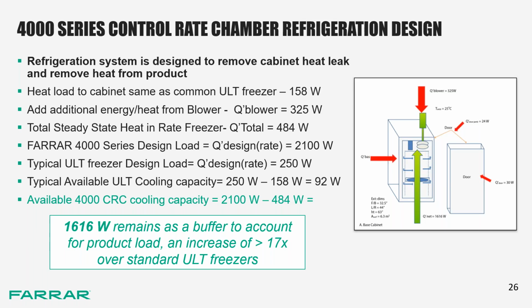As a forced air convection freezer, the Model 4000 also has to consider the additional heat source from its blower, which contributes another 325 watts, bringing the total heat load inside the chamber to 484 watts.